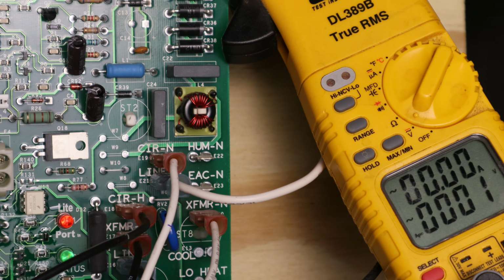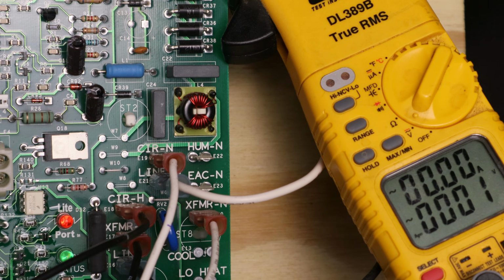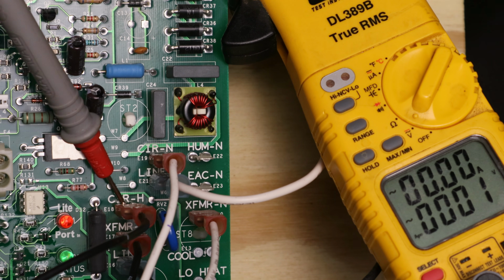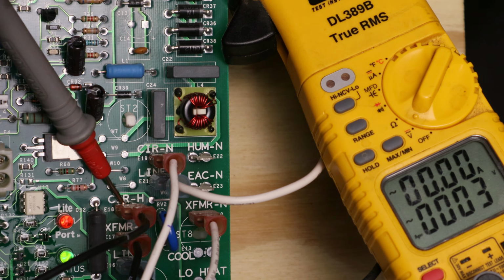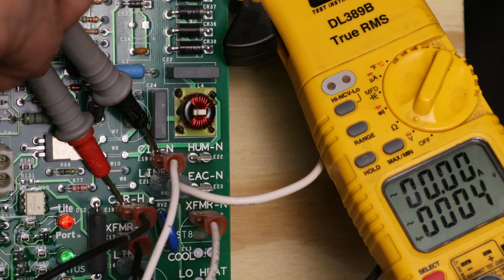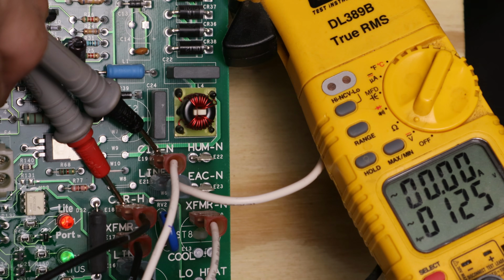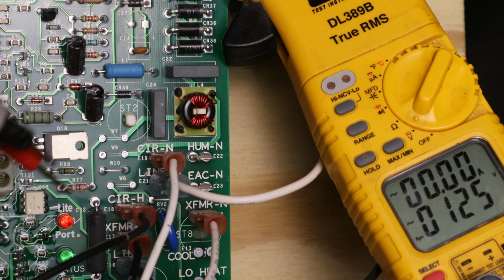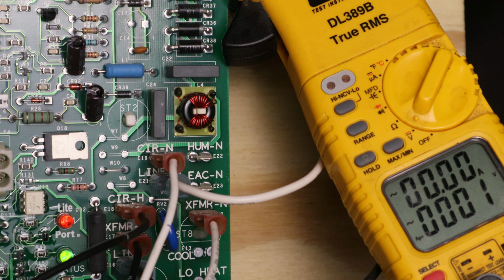Now, if I'm not getting power at my motor, next thing I want to check is that the board itself is putting power out. So I'm going to go ahead and check between the hot wire on the circulator and the neutral. And I'm getting 125 there. If I wasn't getting 125 there, I would start suspecting the control board is bad because I already know I have 120 volts coming in. Otherwise, I wouldn't have 24 volts down below in my earlier test. Now, if I was getting 120 volts off the board, but I'm not getting it at the motor, then it's time to ohm out those wires.